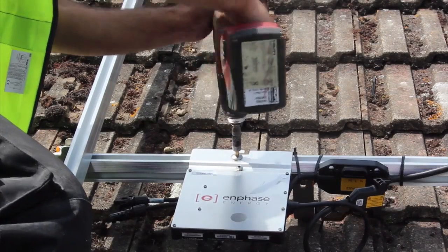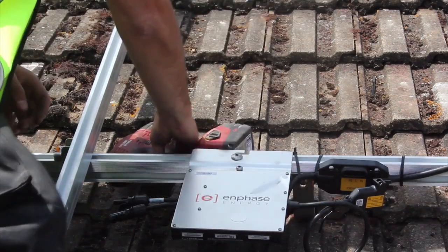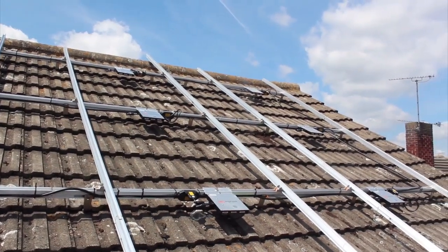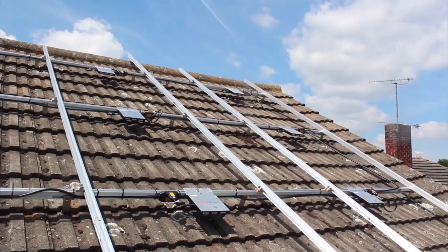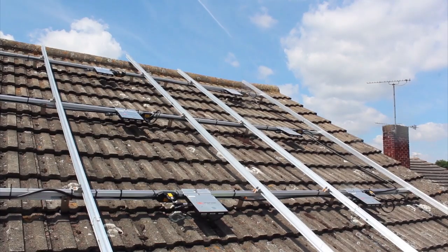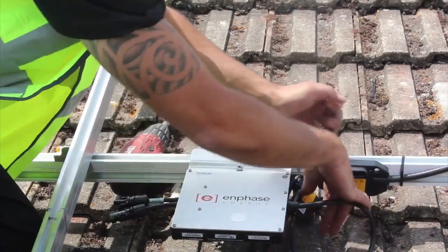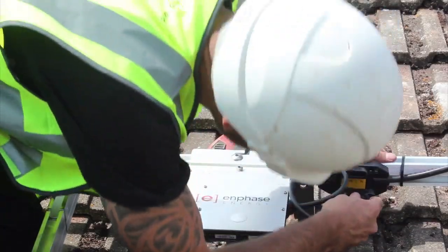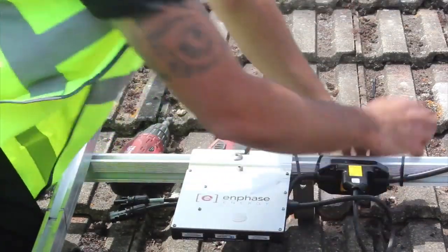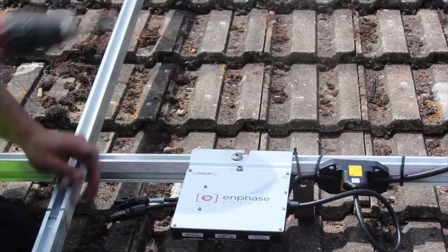Fix the microinverters to the rails with a standard M8 bolt, using one bolt and washer per inverter. The inverters can be fitted in various positions on the rails. The main thing to remember is to get them the right way up, with the Enphase branded silver side facing the back of the module. Next, plug the microinverters into the AC drop connectors on the Engage cable. Listen for two clicks as they engage — both latches must engage to get an IP67 rating.